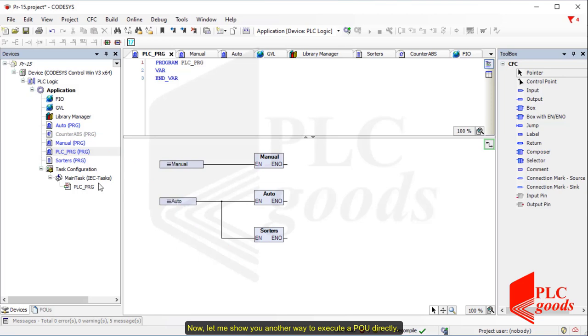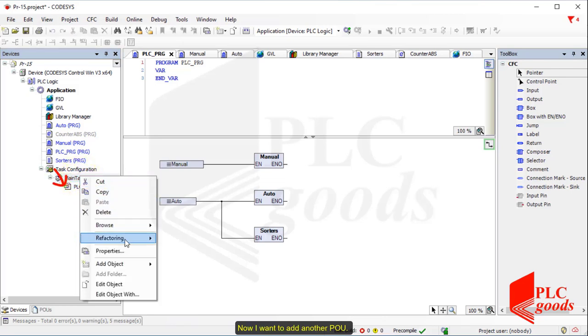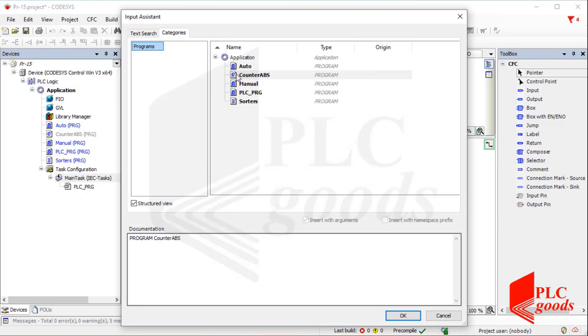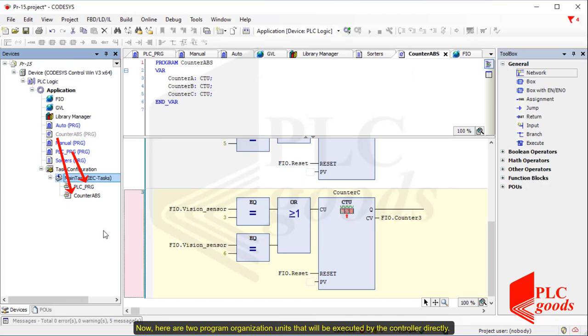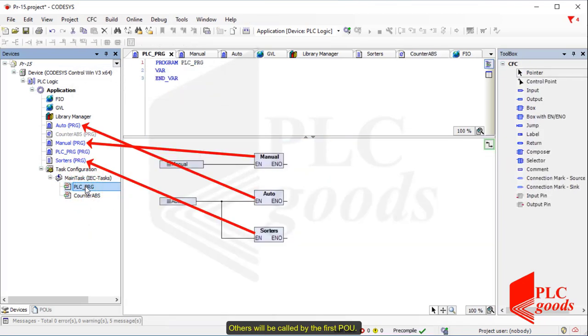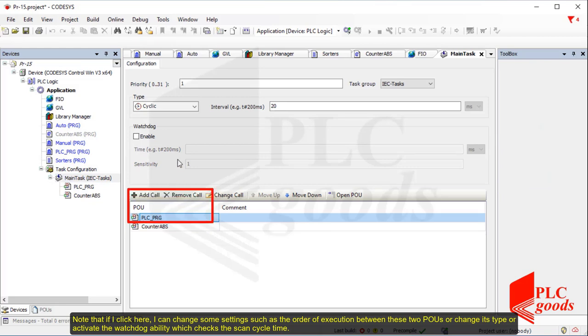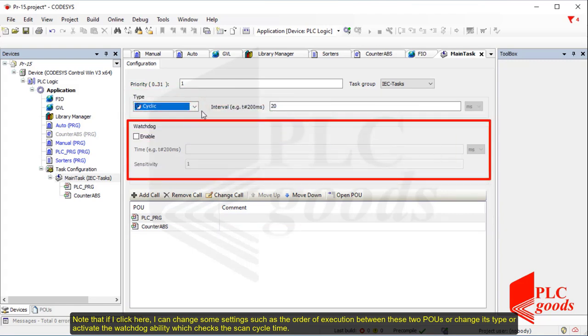Now let me show you another way to execute a POU directly. Note that the controller starts its work from this POU. Now I want to add another POU. Now here are two program organization units that will be executed by the controller directly; others will be called by the main POU. Note that if I click here, I can change some settings such as the order of execution between these two POUs, change its type, or activate the watchdog ability which checks the scan cycle time.